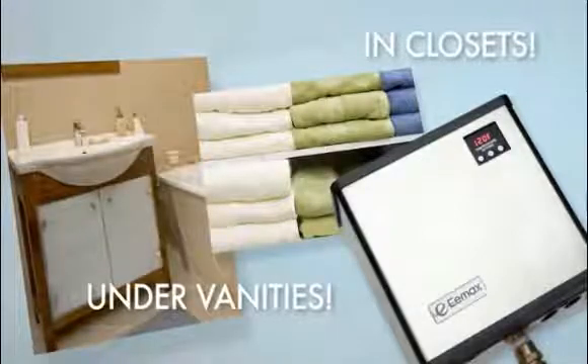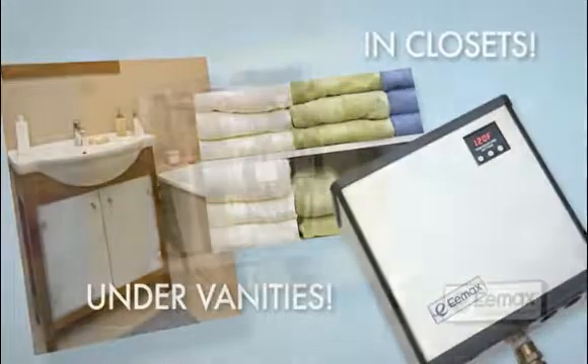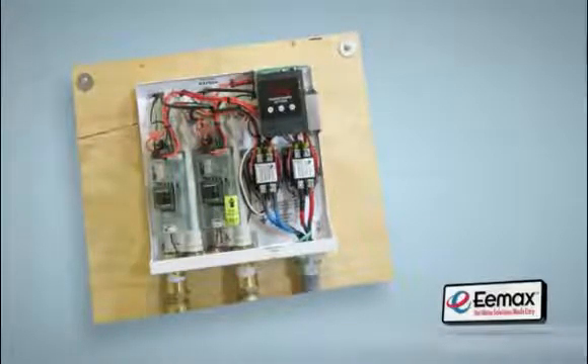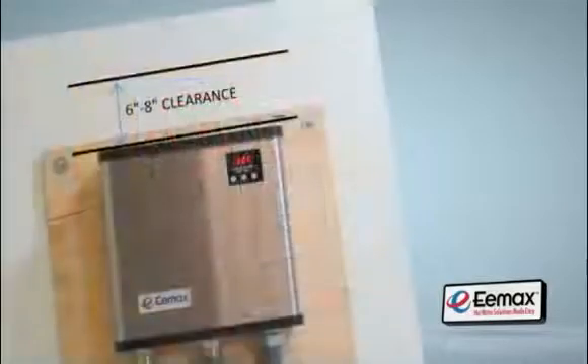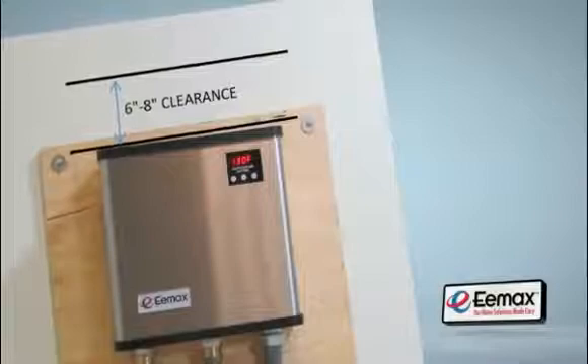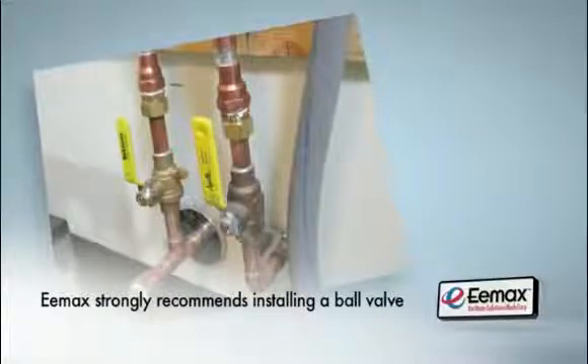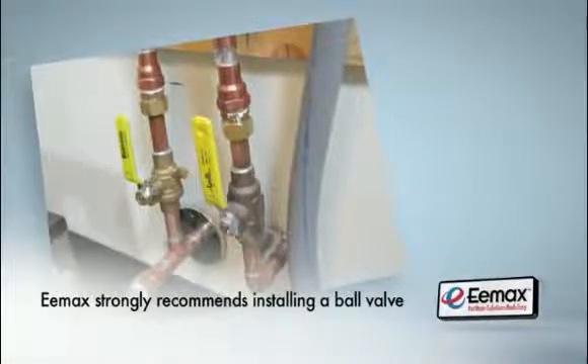But make sure the heater is in a location where it's not exposed to freezing temperatures. For greatest efficiency, mount the heater at or near the point of use. Install the unit so it is very secure to the wall. You may use plywood as a backer — this is also the case when mounting to a cement wall. Always allow 6 to 8 inches of free space above the heater for maintenance access. Eemax strongly recommends installing a ball valve on the inlet and outlet water lines, which will ease installation as well as future maintenance.